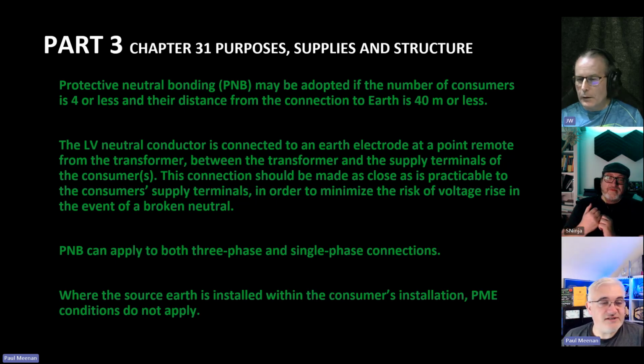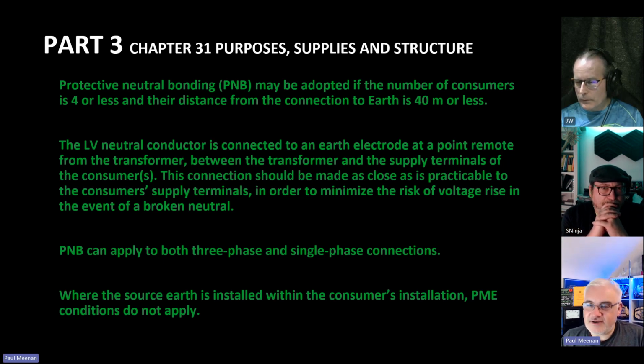So just on that, protective neutral bonding may be adopted if the number of consumers is 4 or less, and their distance from the connection to earth is 40 meters or less. I don't know where this has come from. This is all new. It's interesting.